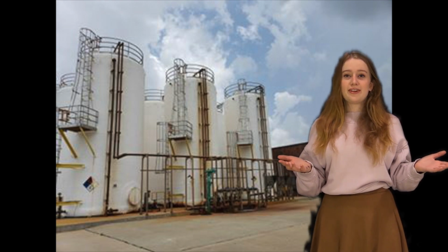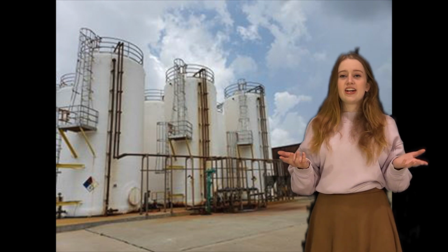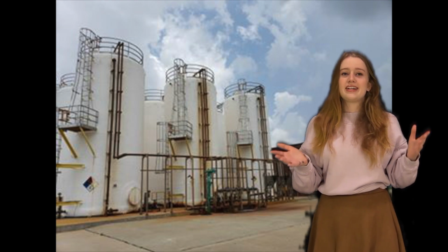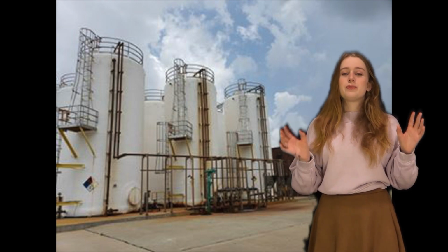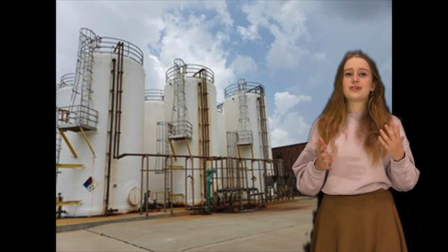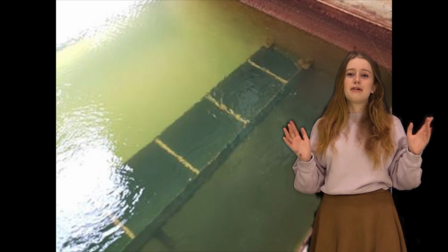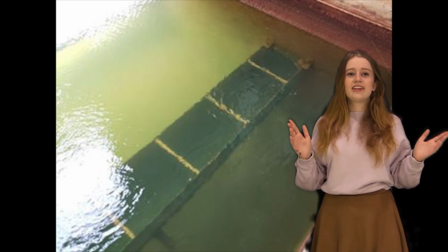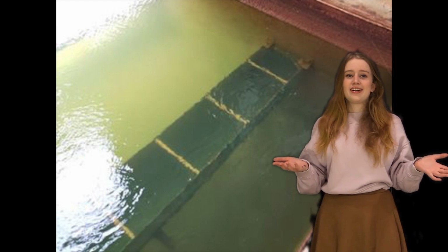So they store the liquid oxygen in huge tanks like the ones you see behind me and turn it into a gas using ambient air vaporizers. Then electrical energy is used to pull apart the O2 molecules and create O3 molecules, or ozone molecules. Then they take this ozone gas and bubble it up through the water in these rectangular tanks. So the ozone oxidizes and disinfects the water.